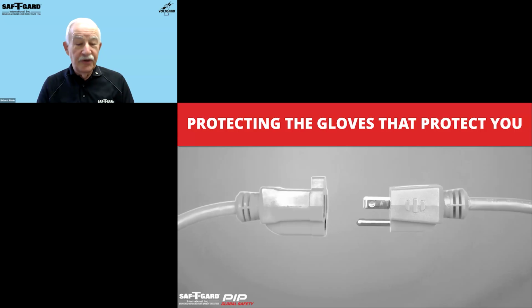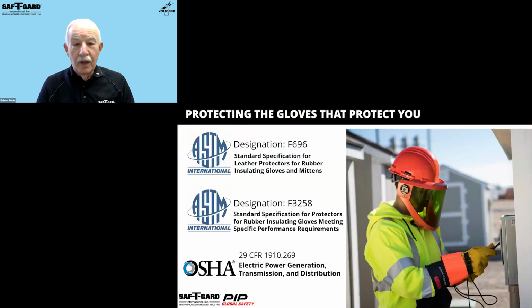Now, you've got to protect the gloves that protect you, because the rubber insulating gloves do most of the job of protecting against electricity, but they don't protect against the physical hazards of the job. ASTM also references 2 standards for protector gloves. ASTM F696 is a design standard that specifies the construction and type of materials that are used in the design of protector gloves, primarily of leather. The new standard, ASTM F3258, is a specification for protectors that goes beyond the F696 standard and requires arc, cut, and puncture resistance testing and reporting with optional abrasion resistance for testing and reporting. In fact, there are protector gloves available that meet both standards.